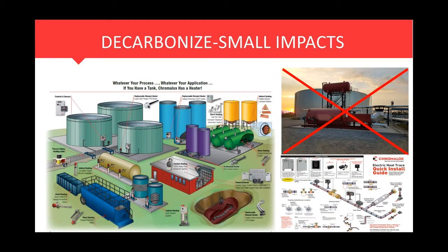That's exactly right, Thomas. And what's interesting is that a lot of what we've been talking about is for larger applications, right? You're talking about a gas-fired hot oil heater or a gas-fired reboiler, glycol regen unit. That could get into the higher BTUs. We're targeting anything around 10 megawatt and lower. That's where we feel Chromalox has a definite advantage. Doesn't mean we can't look at higher KWs as well, but 10 megawatt and lower seems to be a good spot for electric heaters from a sizing standpoint and cost standpoint. But again, we can increase up to larger sizes as well.